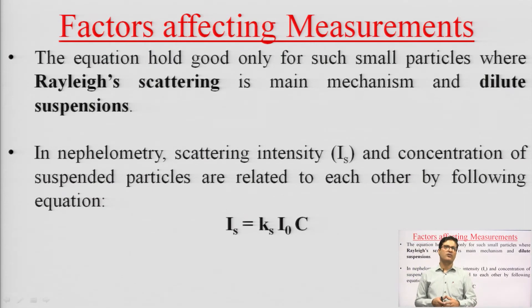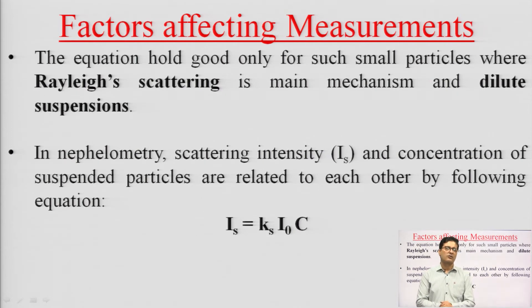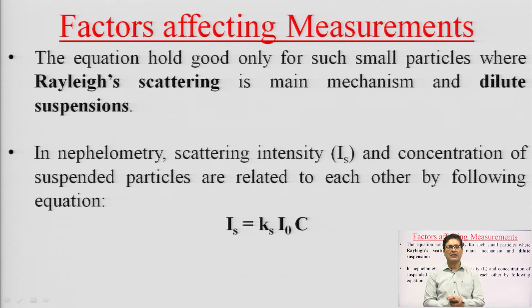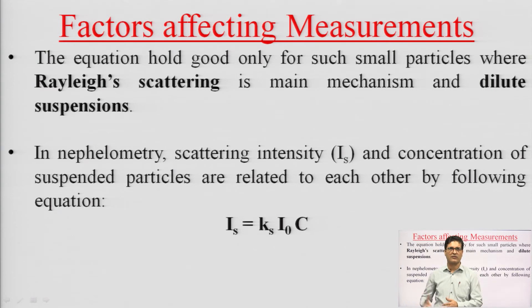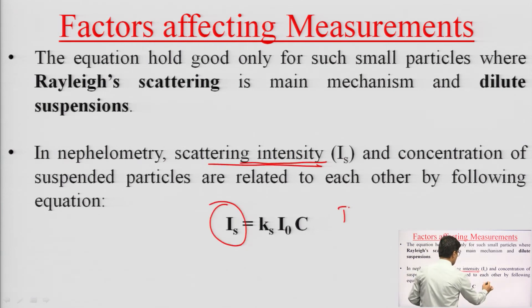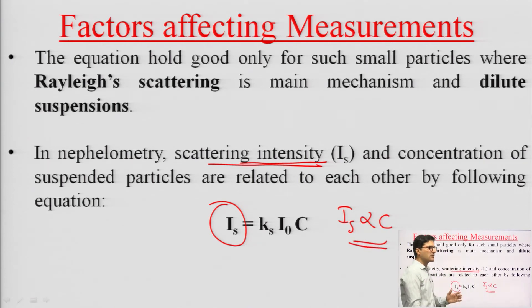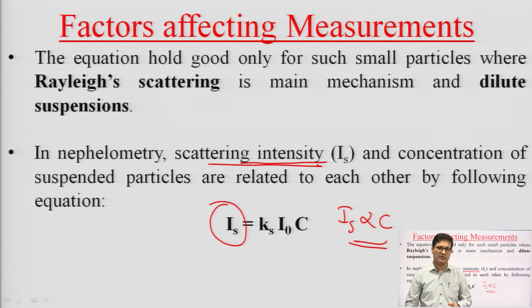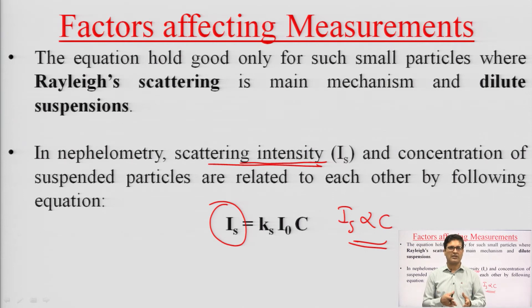This equation holds good only for small particles where Rayleigh scattering is the main mechanism, and for dilute solutions. In nephelometry especially, when the solution is very dilute, this law is most suited — similar to Beer's Law, which is also applicable to dilute solutions. As concentration increases, other mechanisms may also participate in the loss of light. Scattering intensity in nephelometry is also related to concentration: higher particle concentration means more scattering and higher scattered light intensity.